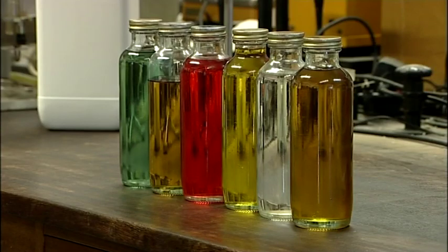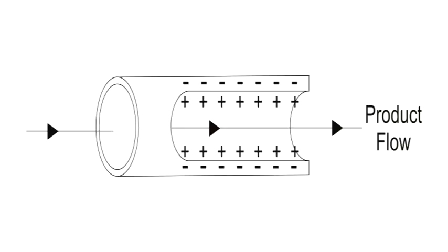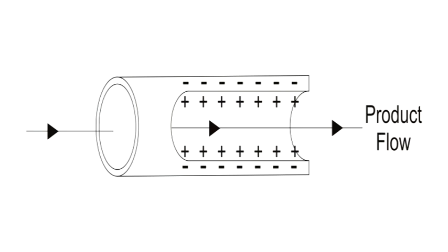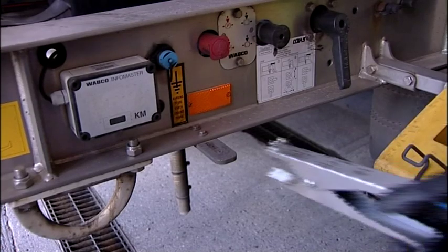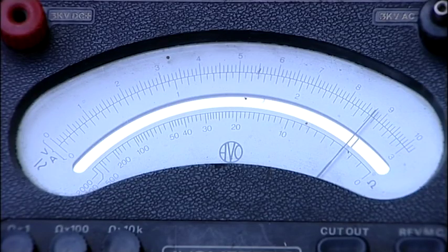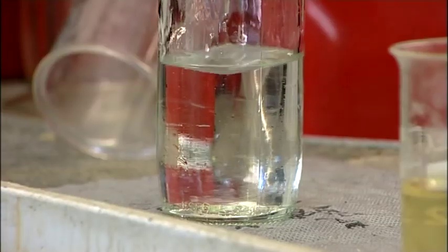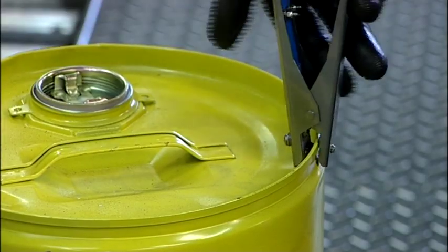If either of the materials is a good insulator or the plant is isolated from earth, electrostatic charge will accumulate. A good example is liquid flowing through a pipe. Negatively charged electrons move across the boundary between the two bodies and are then unable to return. The charge on the containment system can be dissipated quickly by earthing, but the charge in the liquid remains and is slowly dissipated, depending on the conductivity of the liquid. How quickly the static electricity charge builds up depends on a number of factors: turbulence of the liquid, the speed and contact of the liquid with the surface area of its surrounding equipment, the presence of impurities, and how quickly the earthing equipment can remove the charge.